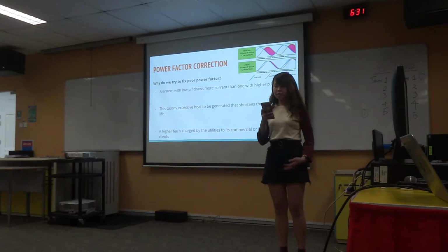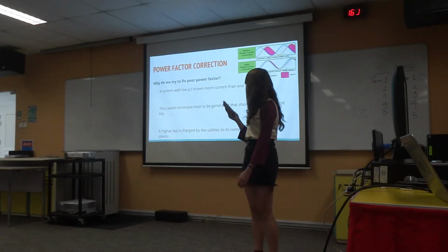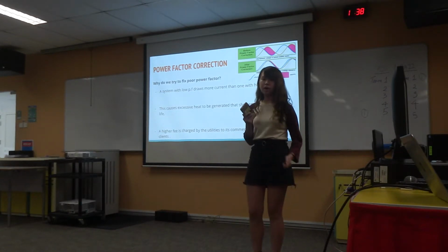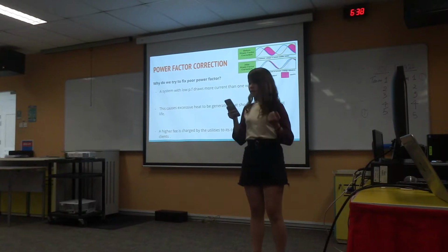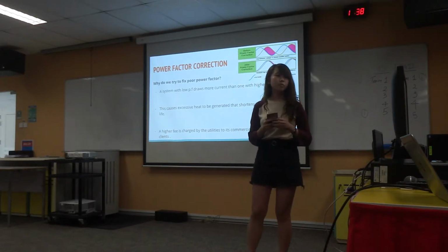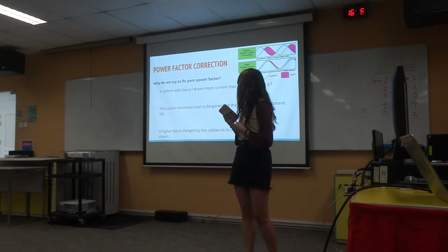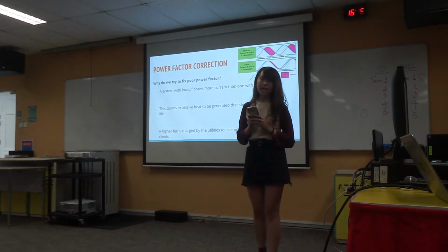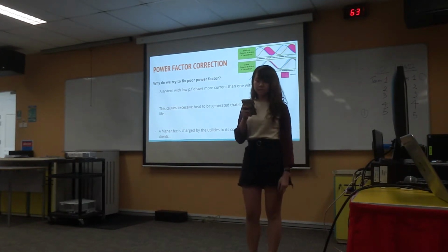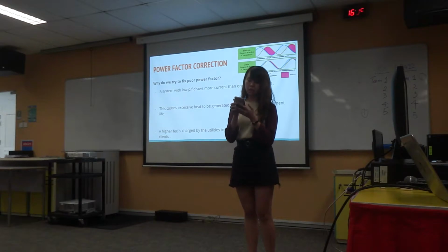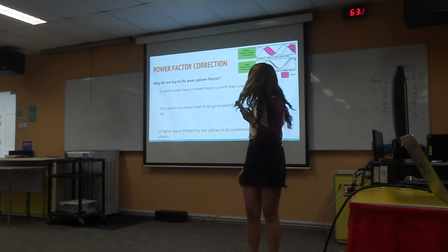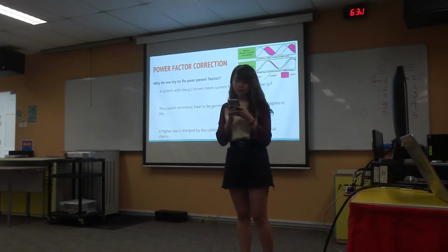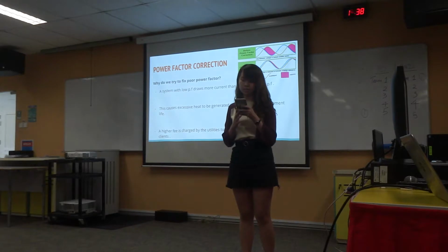So why do we try to fix poor power factor? This is because a system load with low power factor draws more current than the one with higher power factor. Therefore, this will increase reactive loads and will reduce the output voltage. With that, it requires equipment to be constructed heavier to absorb the internal energy. Thus, this will result in a more expensive system with equipment able to absorb larger load system. Lastly, utilities will charge pricier to industrial clients, which is why poor power factor has to be fixed.